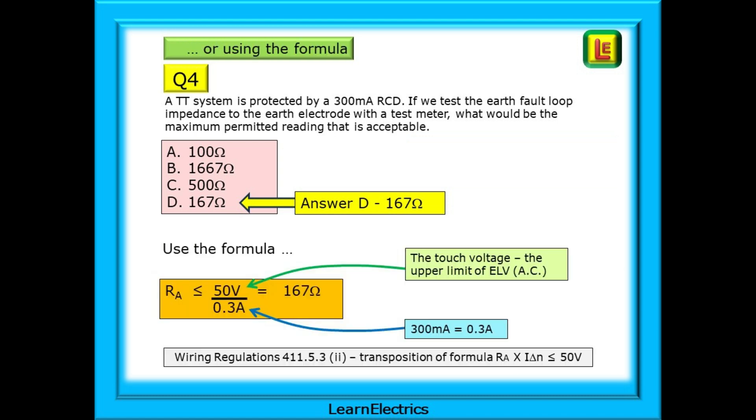Or we can use the formula found in the Wiring Regs book in Regulation 411.5.3 Part 2. An easy transposition of this formula will make the resistance the subject. Look at the formula in the orange box. It is just Ohm's law. Resistance equals voltage divided by current.